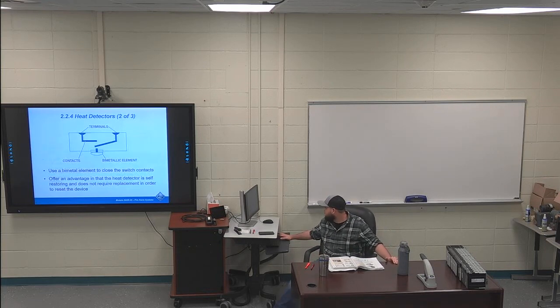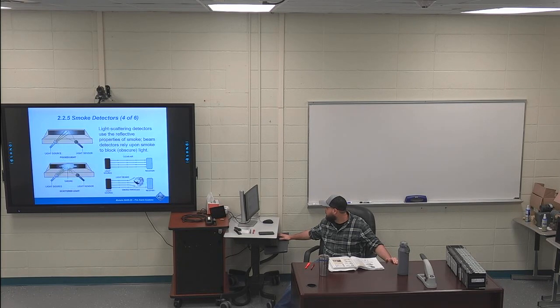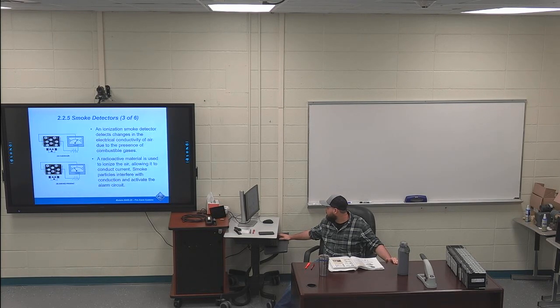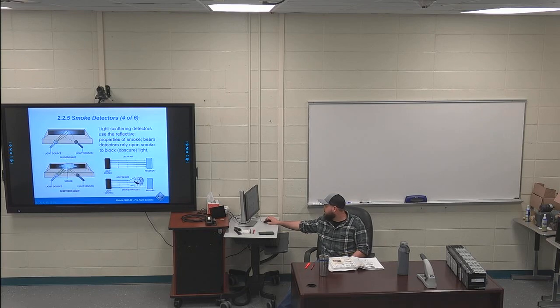If you look at figure 16, oh, here it is. Figure 16 right here. I have a light source and a receiver. Clear air, light source is received by this receiver. If there's smoke, the light particles bounce off the smoke. The receiver doesn't receive anything, and then it initiates, saying there's smoke wherever it's looking at that.